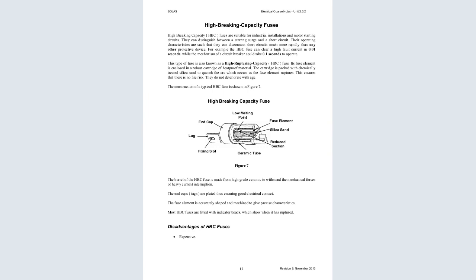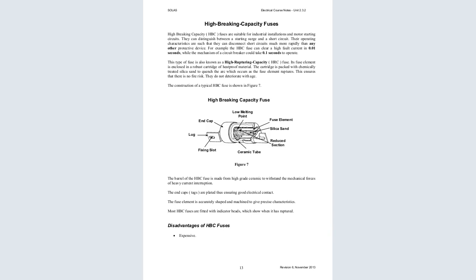Now the high breaking capacity fuse. The high breaking capacity fuse, also called the HBC fuse, is suitable for industrial installations and motor starting circuits. It can distinguish between the starting surge and the short circuit. Its operating characteristics are such that it can disconnect short circuits much more rapidly than any other protective device. So HBC fuses are very important for the three-phase because they act very fast. For example, the HBC fuse can clear a high fault current in 0.01 seconds. You can imagine how fast that is. So it can avoid fire or burning of devices like motors, while the mechanism of a circuit breaker would take 0.1 seconds to operate.